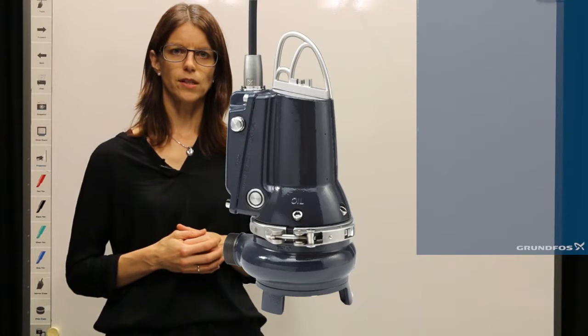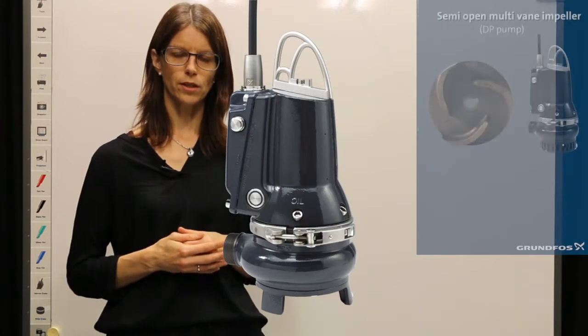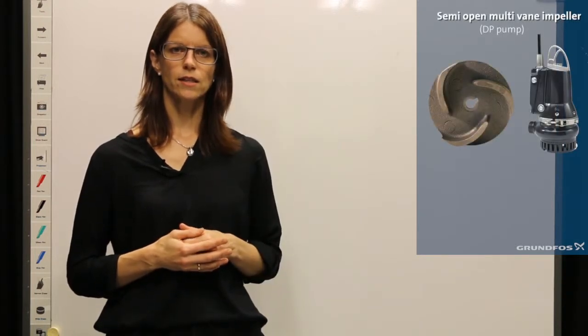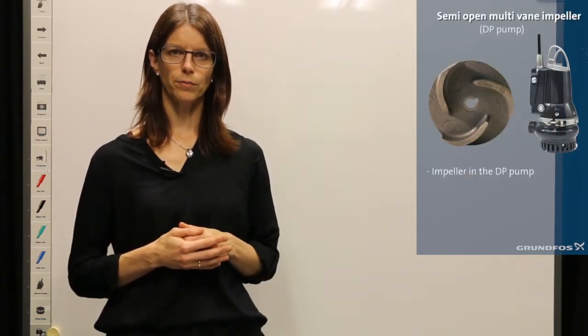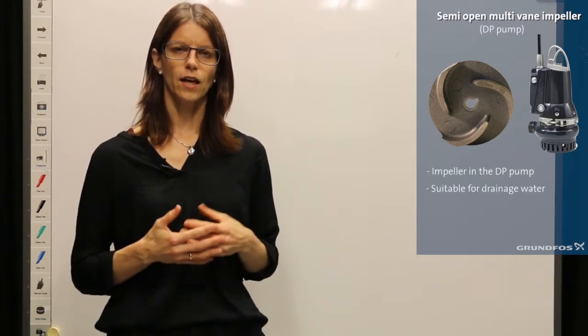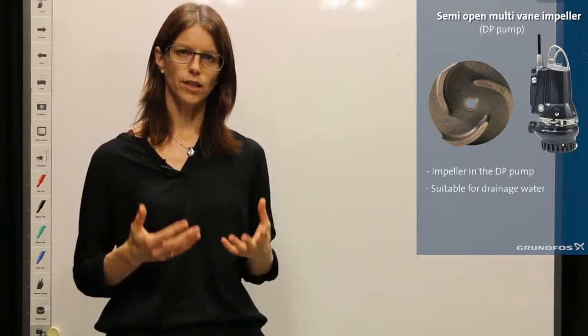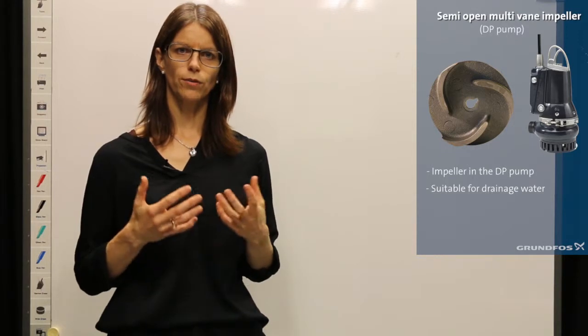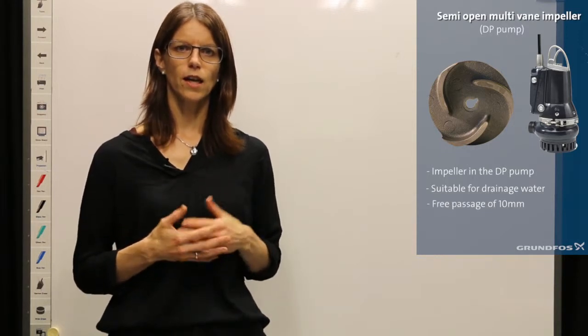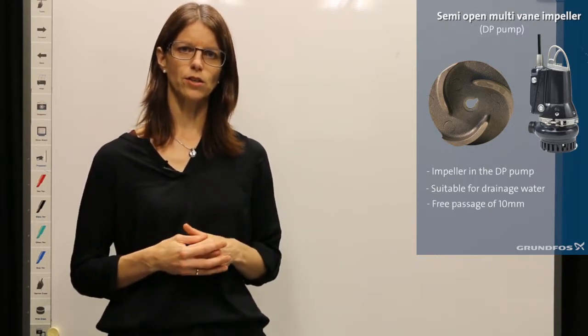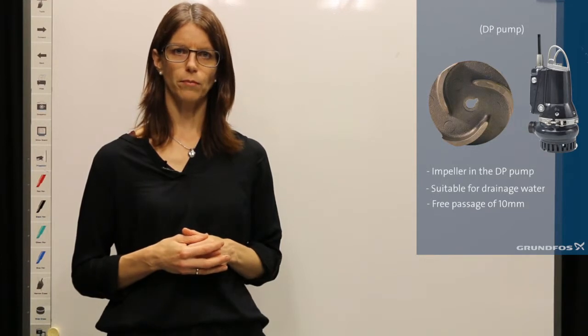First we have the semi-open multi-vane impeller. This is the impeller in the DP pump, and it is suitable for handling drainage water with very small particles. It has a free passage of 10 millimeters.